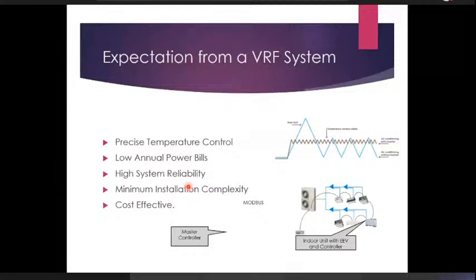And in the off cycle, the air picks back the moisture that was condensing, because there were drops of water on the coil, and then we switch off the compressor because we met the dry bulb temperature requirement of the room. Then the air starts to pick that water back and throw it into the room. In a variable speed system where the compressor changes speed, it is always running. So we could be reducing the amount of moisture removal in the room, but it will never be re-evaporated. That's one advantage which is not listed here, but you should know that.